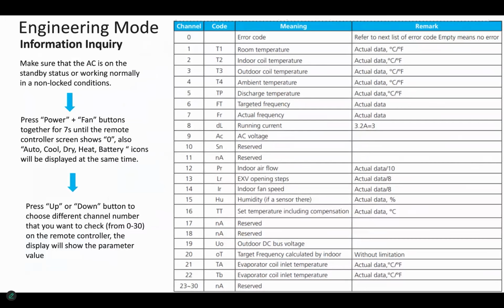If you're not in an error code, it's going to show a little small n, capital A. 1 is your T1 temperature. 2 is the indoor coil. 3 is the outdoor coil. 4 is the ambient temperature. 5 is the discharge temperature of the compressor. 6 is your calculated frequency, or the target frequency. 7 is the actual frequency. 8 and 9 are the running current and the AC voltage. Those will show you actual data.